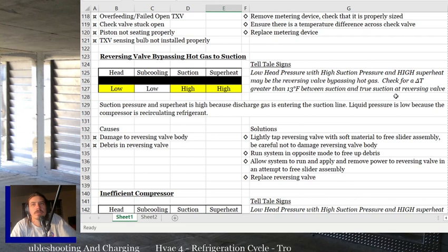So the suction pressure and superheat is high because the discharge gas is entering the suction line. The liquid pressure is low because the compressor is essentially just recirculating refrigerant. So the thing with the superheat being high is the superheat's not really high, right? Well, it kind of is, but it's really not. The superheat's not high because you're picking up heat from the evaporator. The superheat is high because you've got hot gas going in there, so it makes the temperature of the line hot.